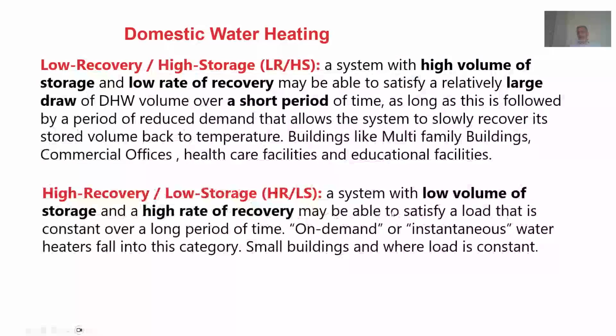The second one is low volume storage and high recovery. Your machine, or the boiler, the one which provides the hot water, is a larger size compared to the volume. It is usually applicable when you are looking for instantaneous heating demand, or where your demand for hot water is constant. It's not changing at all. So you prefer having a high recovery and low storage machine.